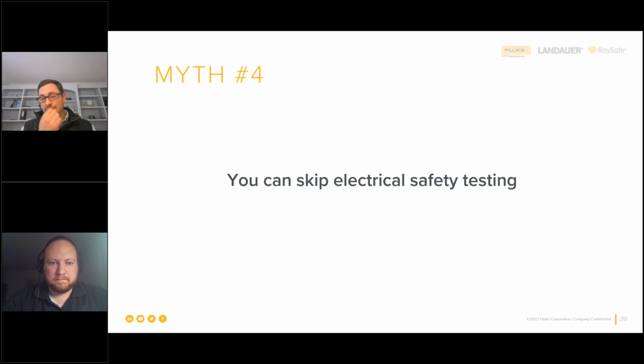And I'd throw out the question: how do you determine that a cable needs to be thrown out or replaced? You can't really determine that if you're not doing electrical safety testing, at least for the applicable cables that would be plugged in. Again, it's a way to see if a cable that's been run over a million times is still working — you can't do that without electrical safety testing. Our point is that a lot can happen over the course of a year, if that's the period over which you're repeating your testing. But if you extend that out to 3 years, 5 years, or even longer, how are you sure your product remains electrically safe for both patients and operators?